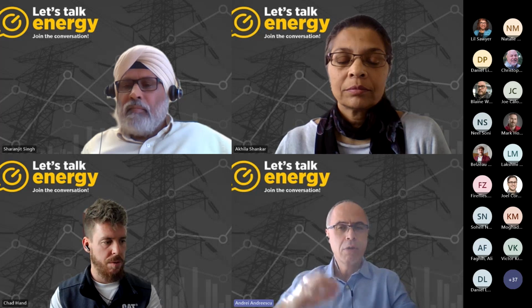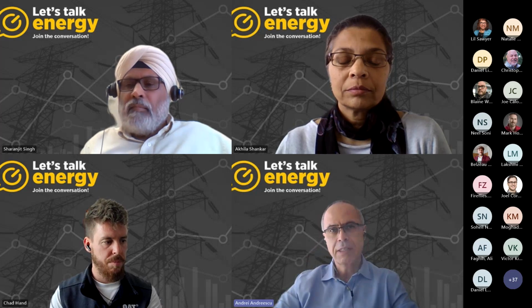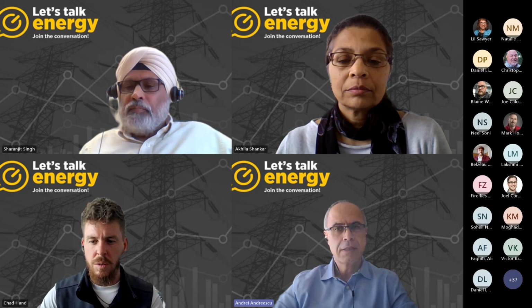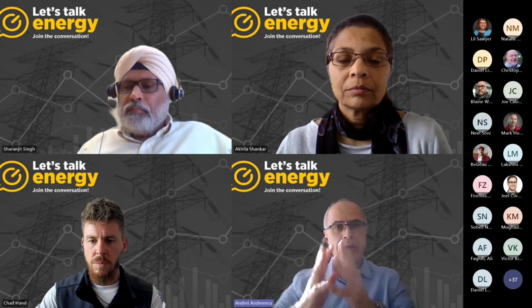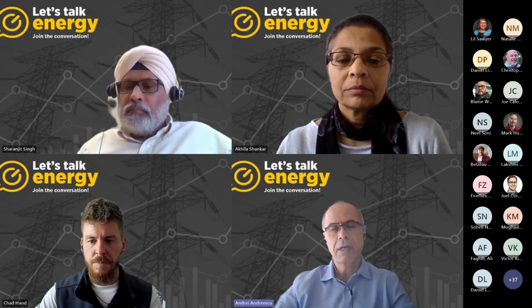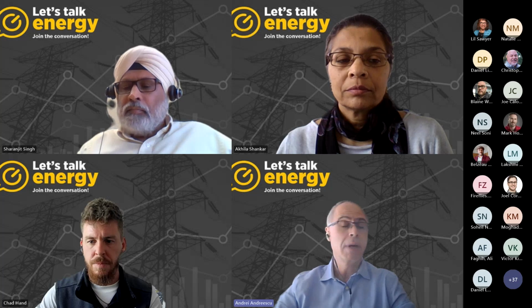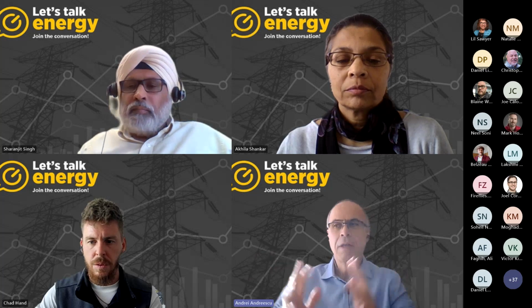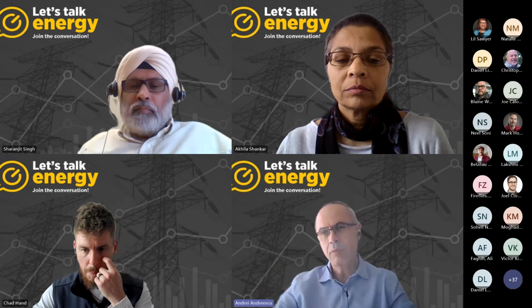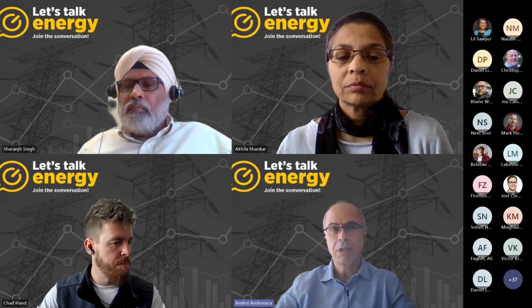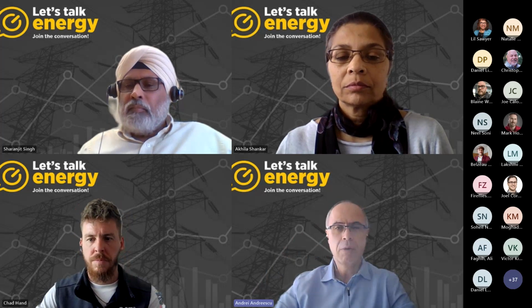The transformer is modeled in the SpecSizer, which, as Akhila said, is a more developed tool than Power Hub. In SpecSizer, you can input the transformer as a load, and yes, it does consider the inrush, the momentary inrush that happens when you start that transformer, but not in Power Hub. Power Hub is for smaller projects, up to 1250 kilowatts right now, so that option is not available in Power Hub.